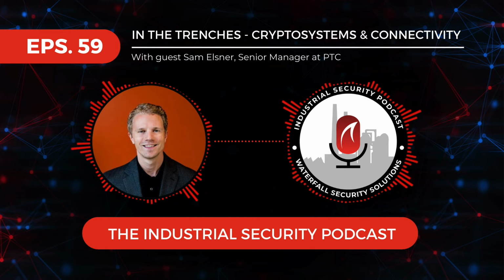So I would say the focus on encryption is useful, but it really should be broken down a little bit too. A protocol that supports encryption needs to do more than that, and most protocols do. So, for example, OPC UA, Unified Architecture, is the latest OPC standard from the OPC Foundation. It uses a security mechanism at the transport layer called transport layer security, TLS. This is a successor of Secure Socket Layer, SSL. The security aspects that transport layer security brings you is unambiguous determination of endpoints. So you will always know that the person you're targeting is who they say they are, guaranteed.